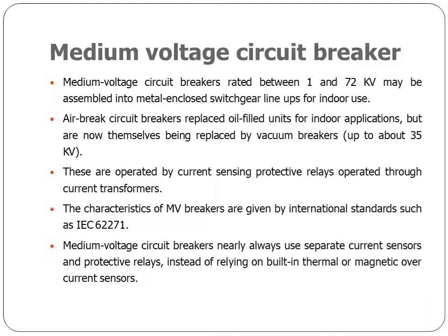Medium voltage circuit breakers. Medium voltage circuit breakers rated between 1 and 72 kilovolts may be assembled into metal enclosed switchgear lineups for indoor use. Air break circuit breakers replaced oil-filled units for indoor applications, but are now themselves being replaced by vacuum breakers up to about 35 kilovolts. These are operated by current sensing protective relays operated through current transformers.